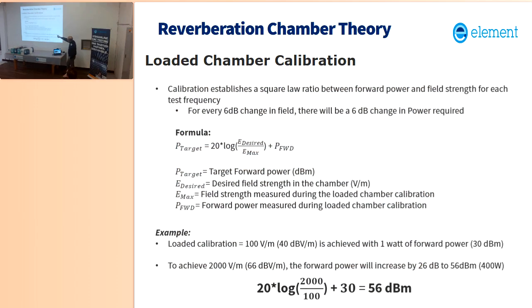So with the loaded chamber calibration, you plug the results into this formula. Bottom line is, when you did the calibration, you come up with that you can get 100 volts per meter for 1 watt of forward power, which is not unusual. Some of the smaller chambers that we have will do that. If your actual test level is 2,000, which is 26 dB more, that means you just need 26 dB more power. So you did the calibration with 1 watt, you got 100 volts per meter. Your test level is 2,000 volts per meter. So you put in 26 dB more, 400 watts, when you run the test at that frequency. You do that calculation for every test frequency. And generally the software does it for you, so that makes it easier.